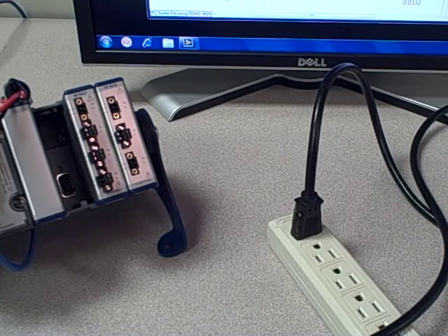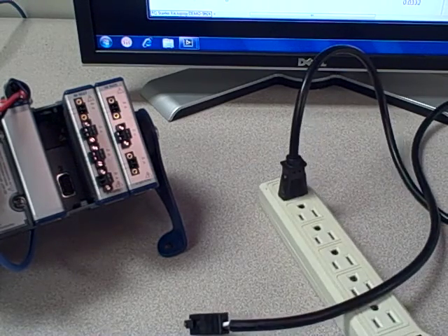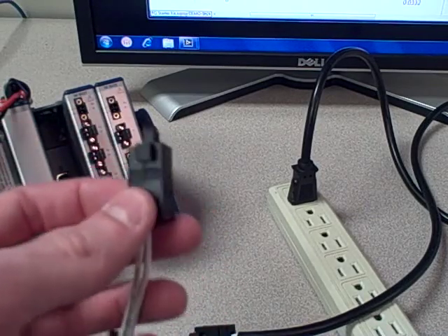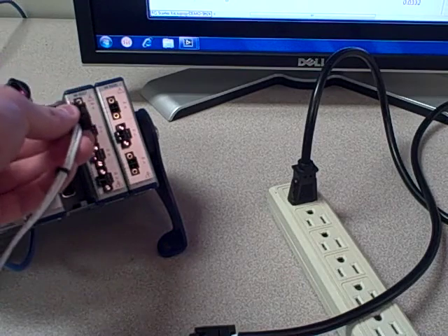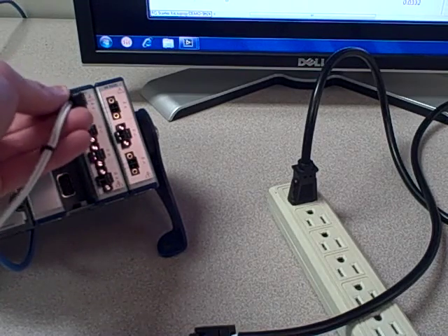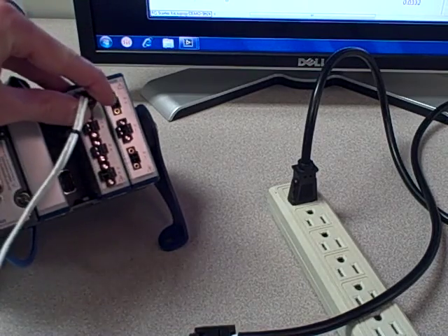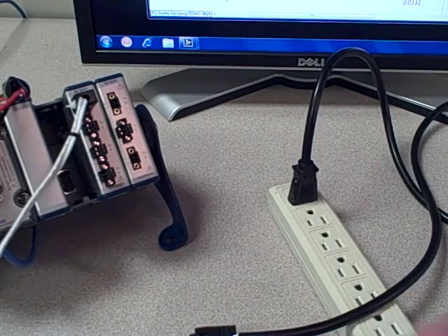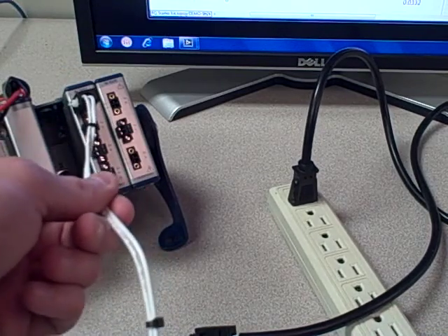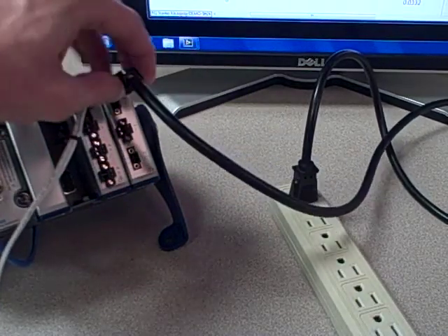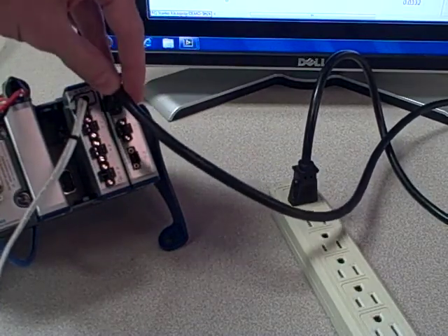Now for power measurements, we're going to have to make some connections to the modules. For this video, I have a power strip that has been spliced so I can make an in-series current measurement. So I'm going to connect my spliced cable into the 9227 module. And now anything that's plugged into the power strip is going to be routed through the cable. And then for a voltage measurement, I have a power cord which is plugged directly into the power strip.